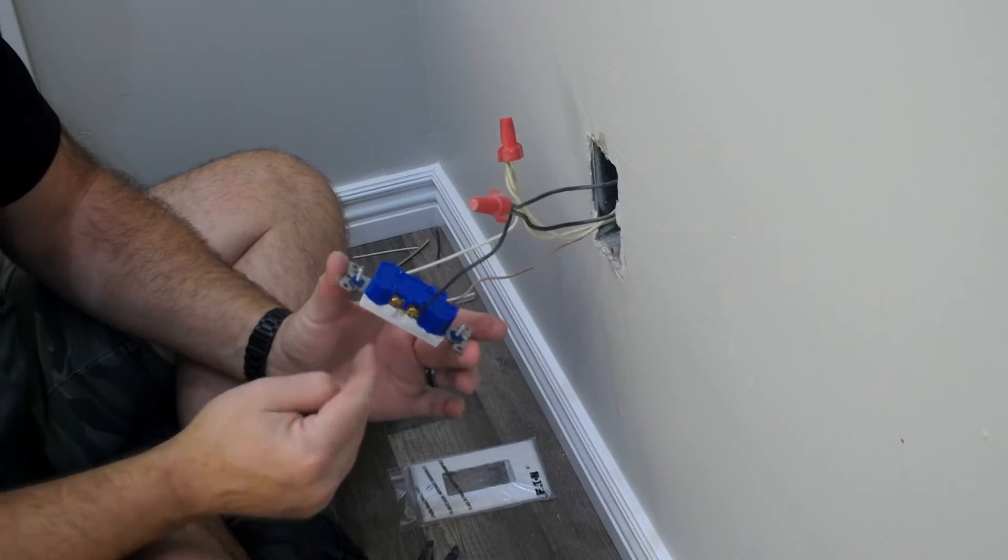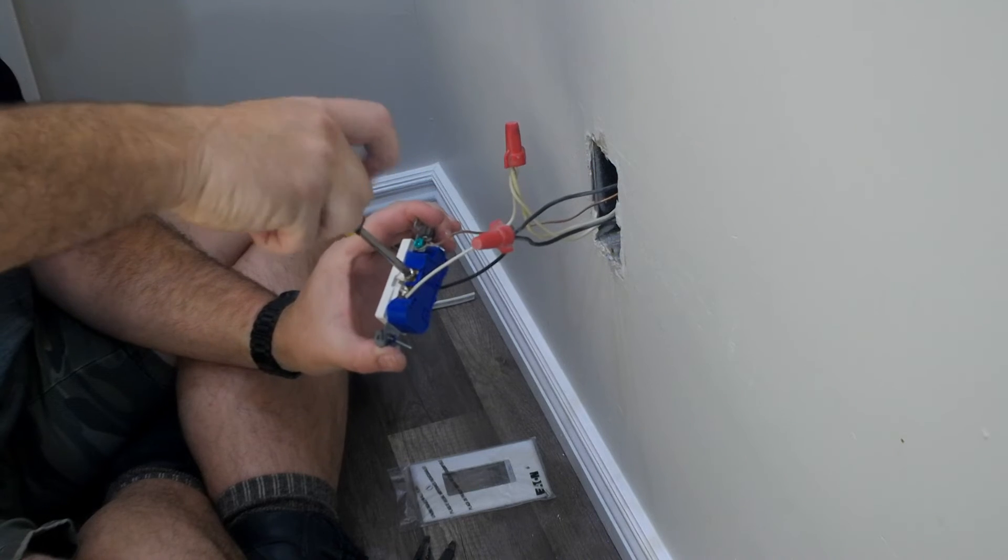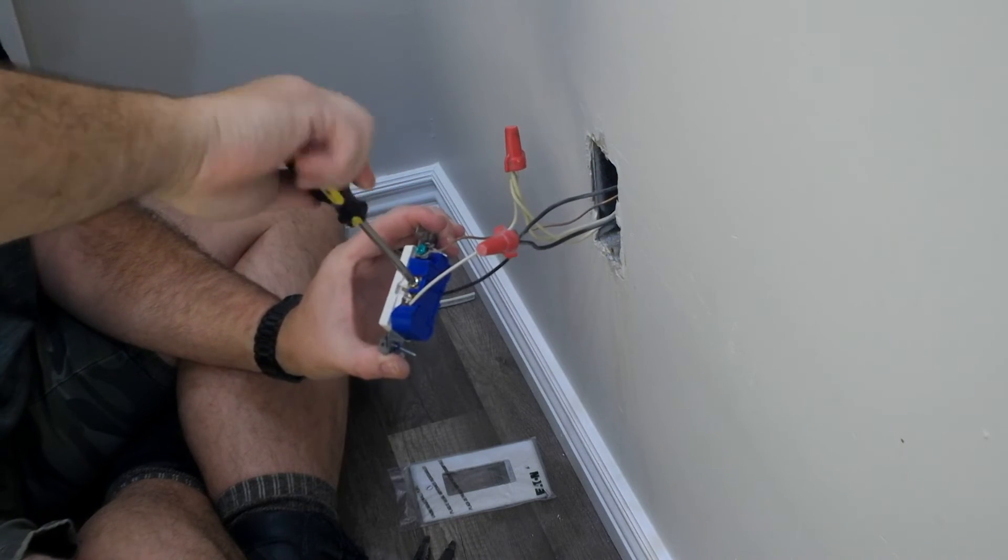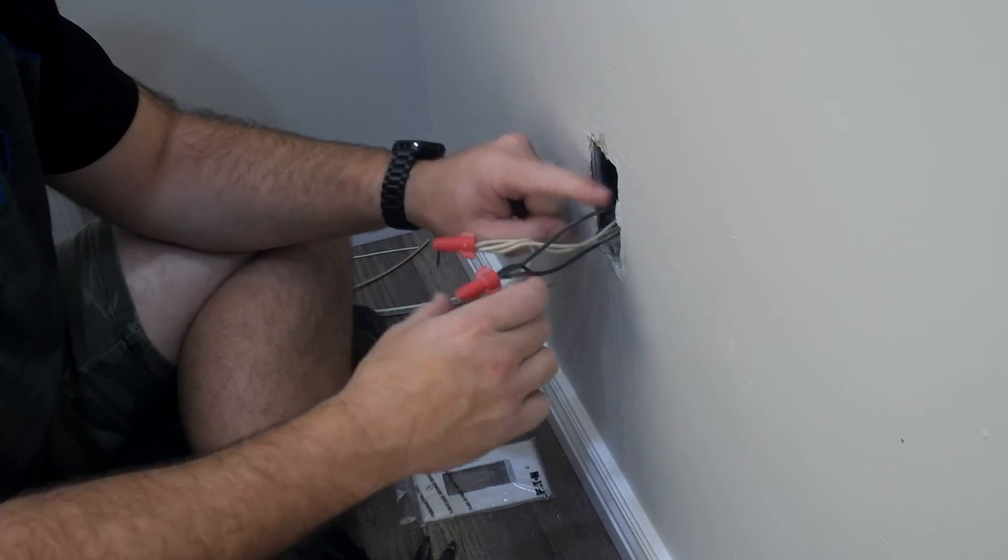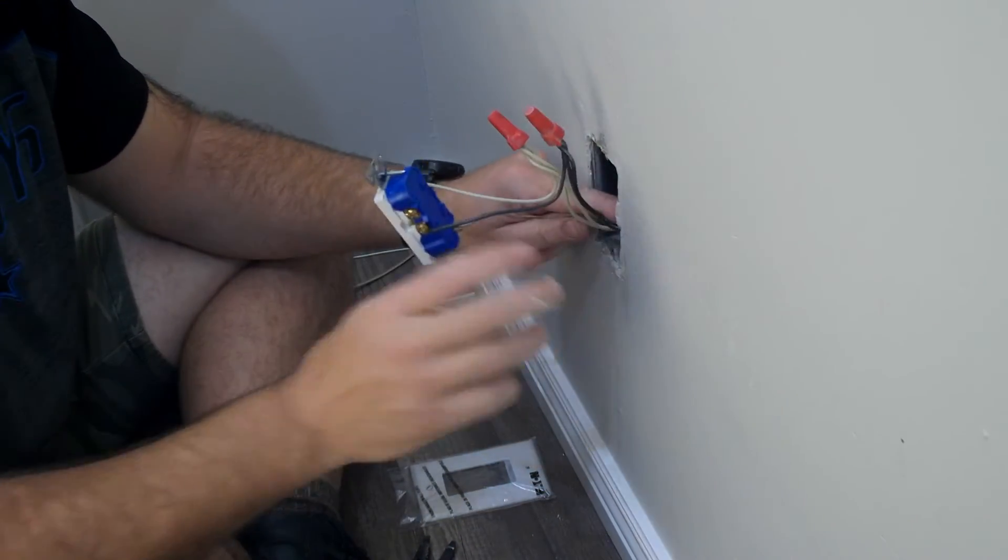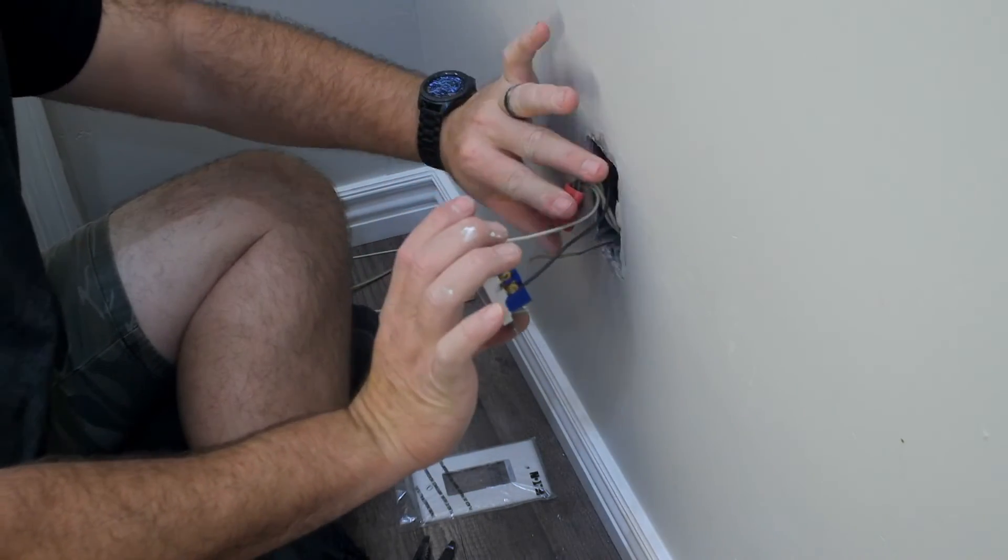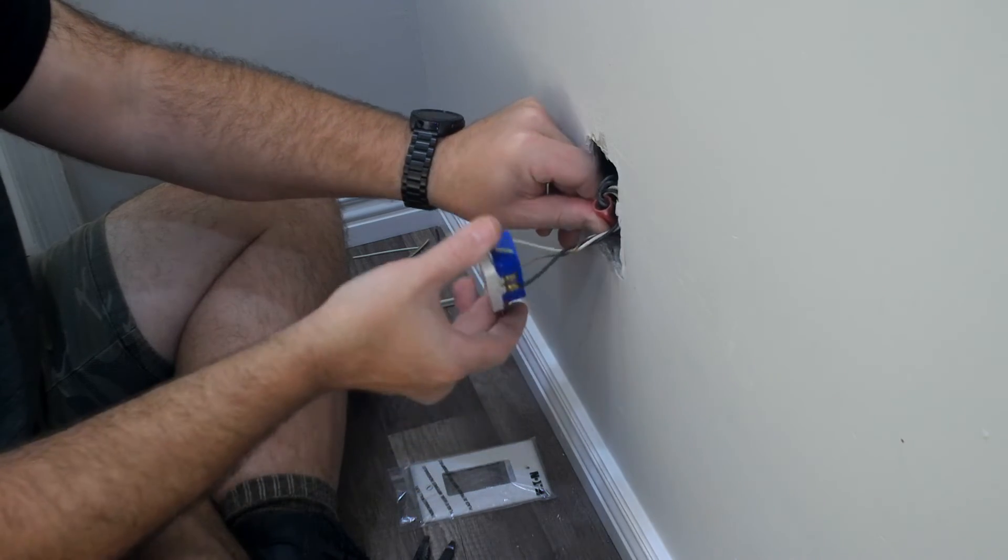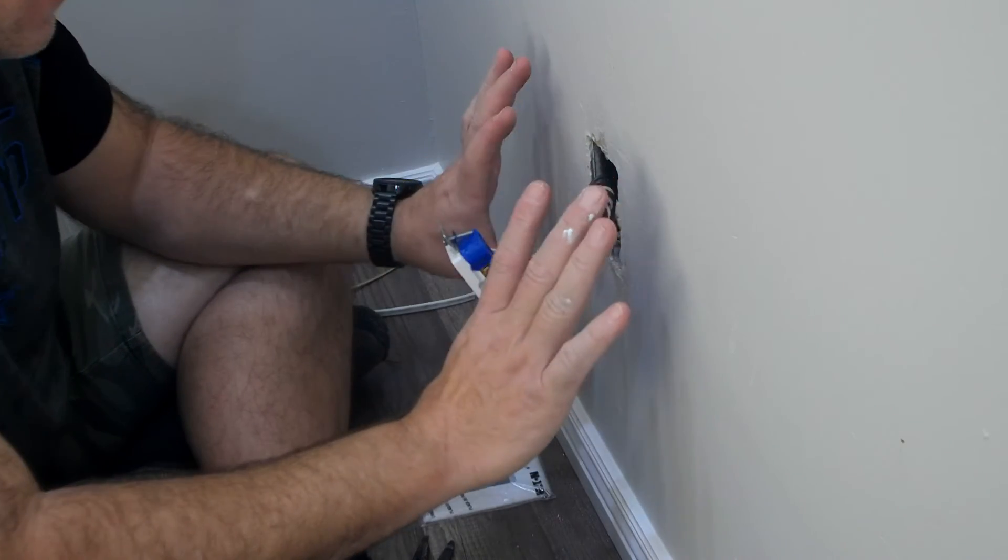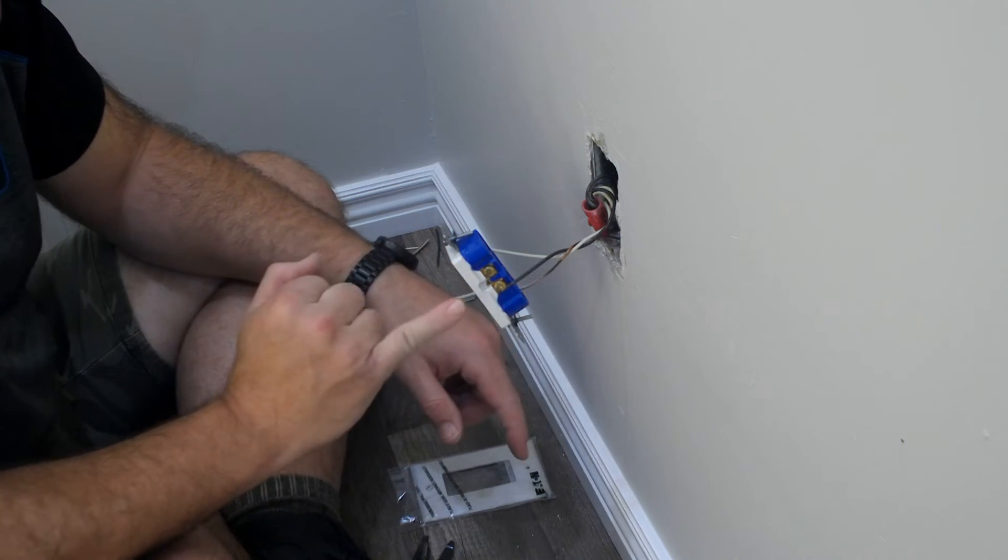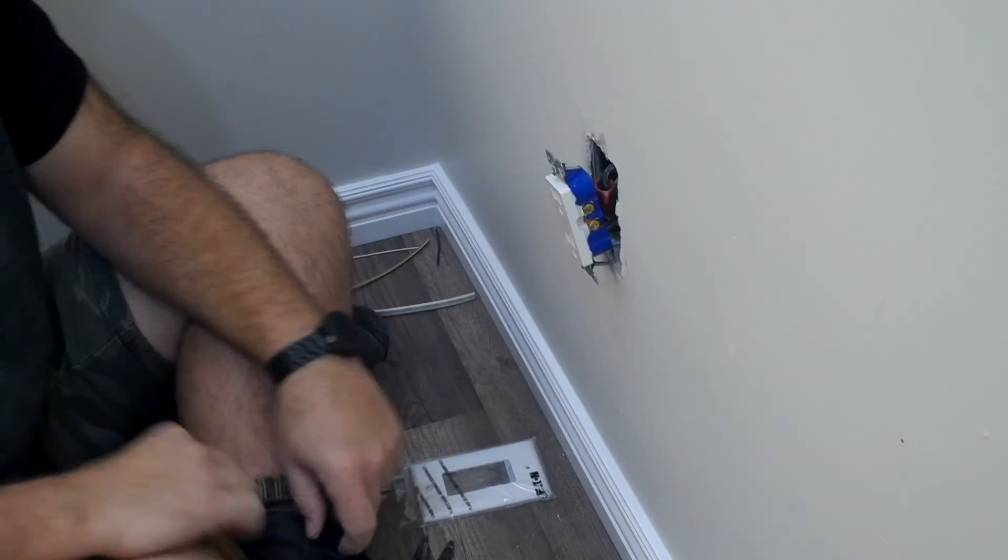Now I've just got to be careful on those screw terminals. Now I forgot to screw that in. We're going to go ahead and screw that in. That's done. So now what we want to do here, we want to bend these wires right in that area. And then it looks like we're going to have to bend these down to get them to tuck in properly. Now before we tuck all of the wires in, we're going to take this and we're going to throw a twist on it. And what that does, you see how this bare ground wire, if you just push all this stuff in there, there's a chance that bare ground wire can come out and contact these terminals right here. By twisting it, we make sure that all the wires travel into the box together.